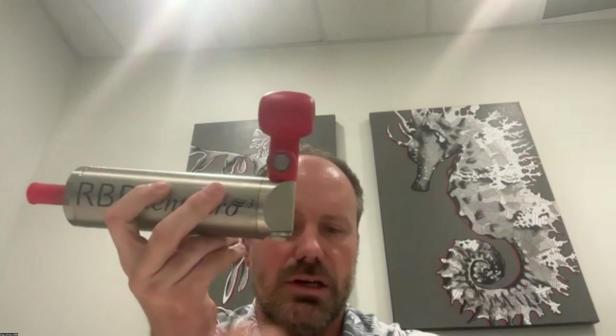The new electronics permit a completely different scheduling for the sampling of the CTD versus any of the other sensors. You could run something once every few seconds, once every 10 seconds, all completely internally. That capability will also be added to our deep water CTD for gliders.